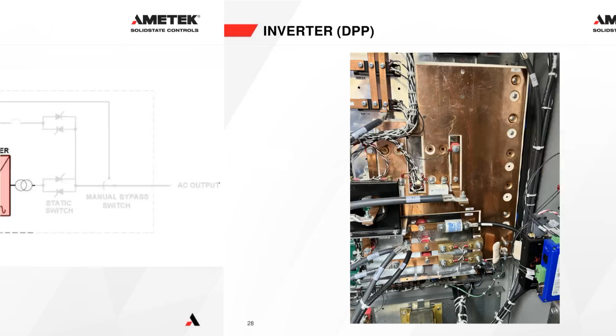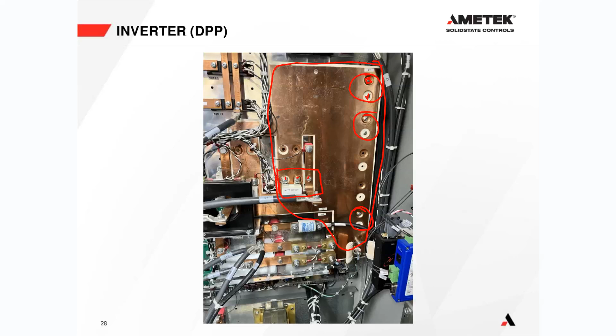So this is our inverter bridge on our single phase 10 kVA DPP system. It's very difficult to see what's going on under there. You can see two terminals here. There's actually a DC capacitor behind there, a DC capacitor behind there, and another DC capacitor behind there. And these three terminals here, there's actually an IGBT module behind there. An IGBT is a transistor, and that's what switches the DC to AC.